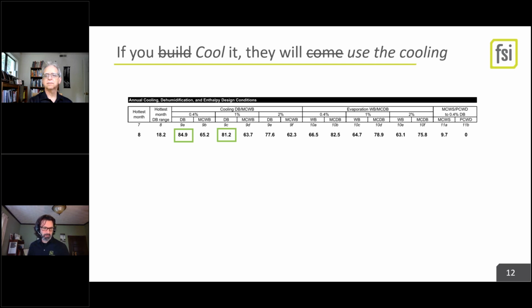So we believe you're going to need more cooling in the future. It is worth saying, and I do get this objection, that with electric resistance heat, if you add cooling, they're going to use the cooling. And I 100% agree with that. If you cool it, they will use the cooling. And you will still be energy ahead over electric resistance heat, says our energy modeling, because heat pumps are so much more efficient. And if you're a developer on the call, you can charge higher rents. So win-win.